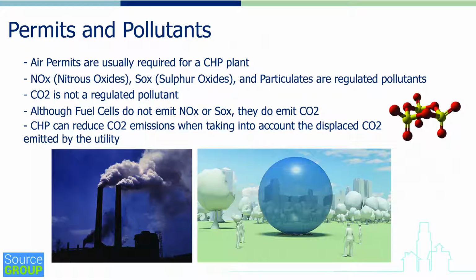Permits and pollutants. Air permits are generally required for a CHP plant. Small plants may have a very simple permitting process that just requires filling out some paperwork and having a fairly short approval time. Larger plants, however, it can be quite complex. If the plant does not meet certain requirements, it can necessitate a so-called PSD permit, Prevention of Significant Deterioration, which is a lengthy process and does take a considerable amount of time.